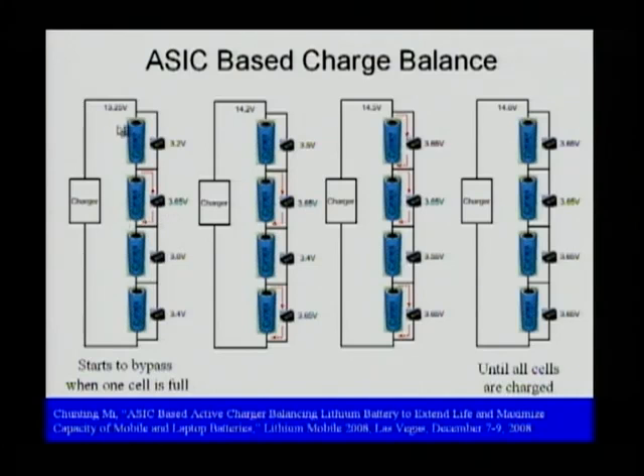During charging, the IC continuously monitors the voltage on the battery cell. Once it sees the cell voltage reach 3.65 volts, it starts bypass current. At the same time, it sends a signal back to the charger saying the cell is already full, so you need to reduce the charging current but keep charging the rest of the batteries. Once the second cell is full, you do the same thing, and the third, until all cells reach 3.65 volts, and then you stop charging.